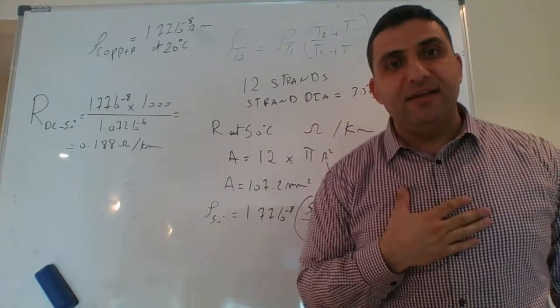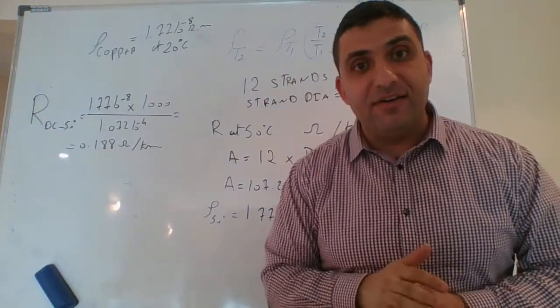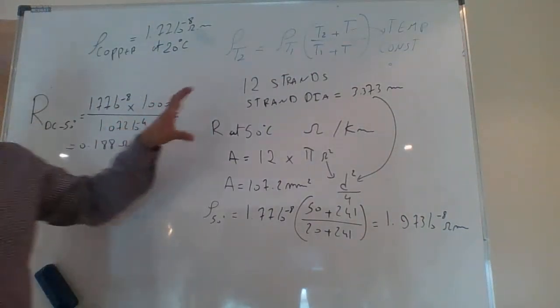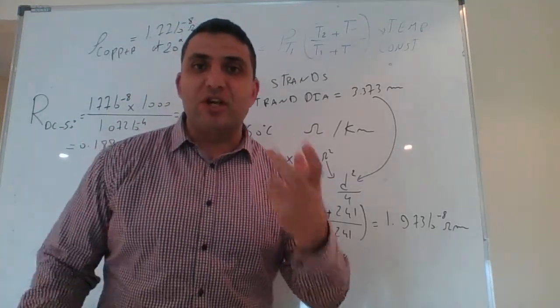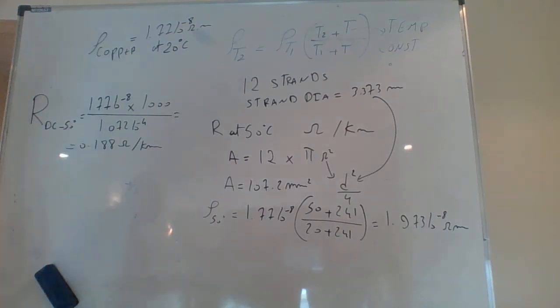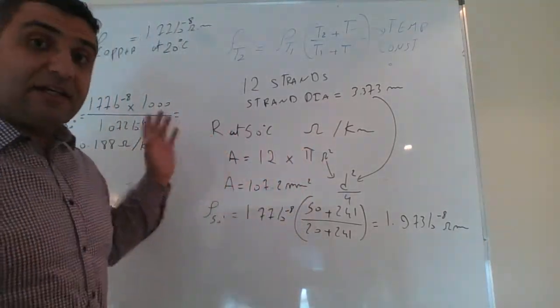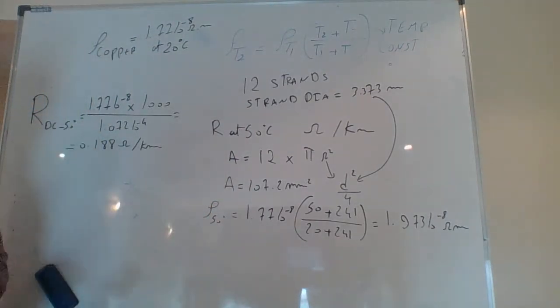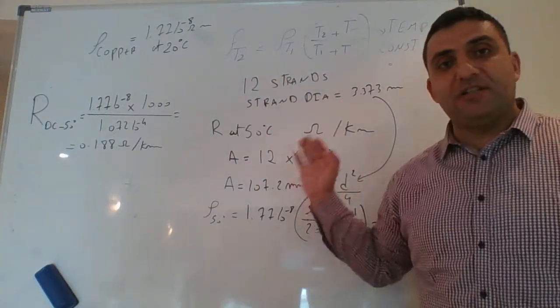It is worth noting that R_dc and R_ac are almost identical — the difference can be neglected. Under AC conditions at 50 Hz, which is not a very high frequency, it is acceptable to consider R_dc as essentially the same as R_ac. The alternating current resistance is very close to the DC resistance at power frequency.